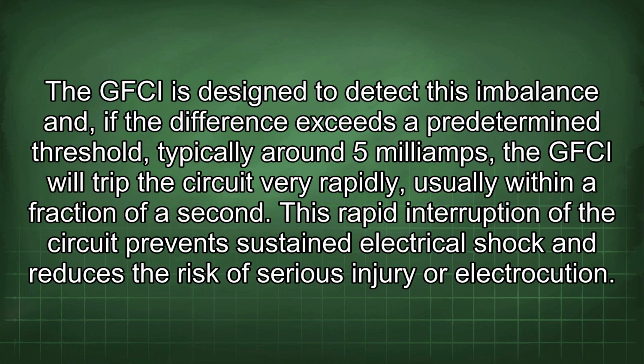The GFCI is designed to detect this imbalance, and if the difference exceeds a predetermined threshold, typically around 5 mA, the GFCI will trip the circuit very rapidly, usually within a fraction of a second. This rapid interruption of the circuit prevents sustained electrical shock and reduces the risk of serious injury or electrocution.